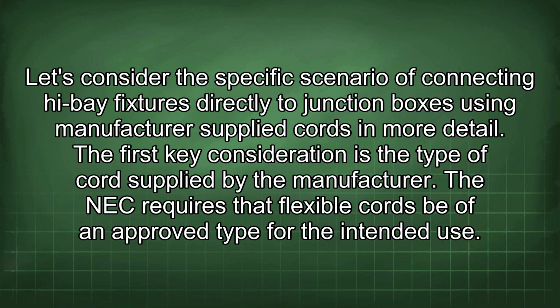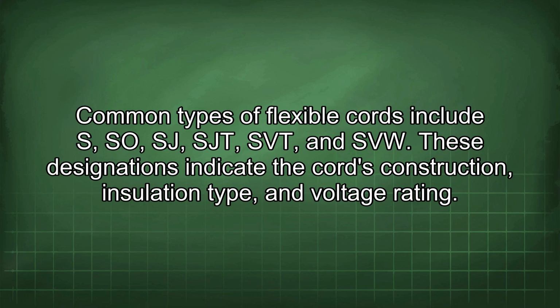Let's consider the specific scenario of connecting high bay fixtures directly to junction boxes using manufacturer-supplied cords in more detail. First key consideration is the type of cords supplied by the manufacturer. The NEC requires that flexible cords be of an approved type for the intended use. Common types of flexible cords include SO, SJ, SJT, SVT, and SVW. These designations indicate the cord's construction, insulation type, and voltage rating.